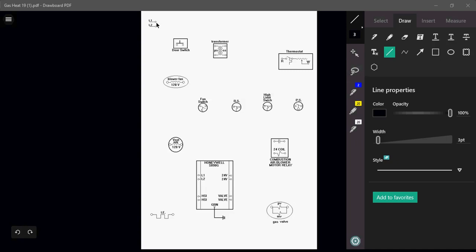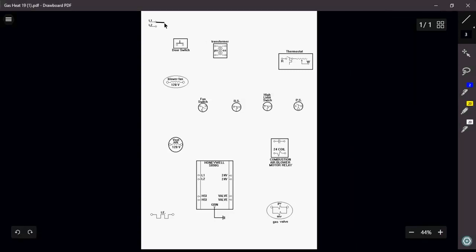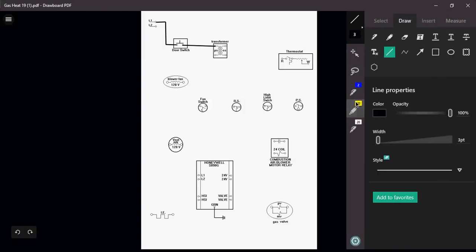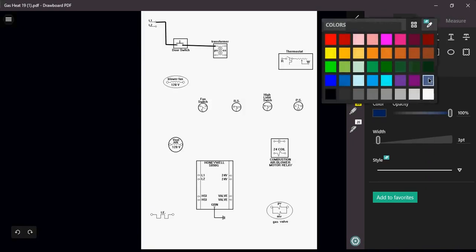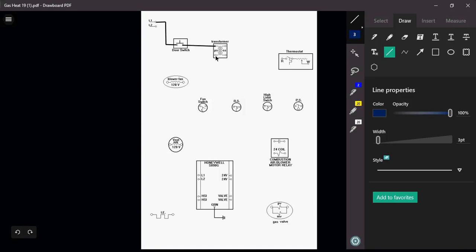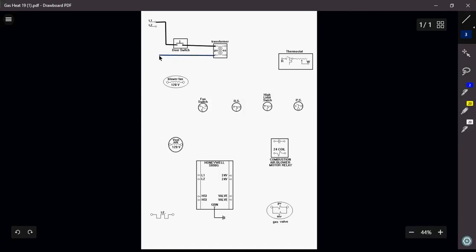So, in order to wire this, we're going to do it very similar to spark ignition. I'm going to come out of my L1, and I'm just going to come down into my door switch. My door switch is also known as my dummy switch. That door switch has to be closed in order for anything else in the system to work. So I'm going to come out of my door switch and power up the primary side of my transformer. Out of my transformer, I'm just going to bring that right back to my L2, just to complete that circuit. So again, everything: source, path, switch, load.